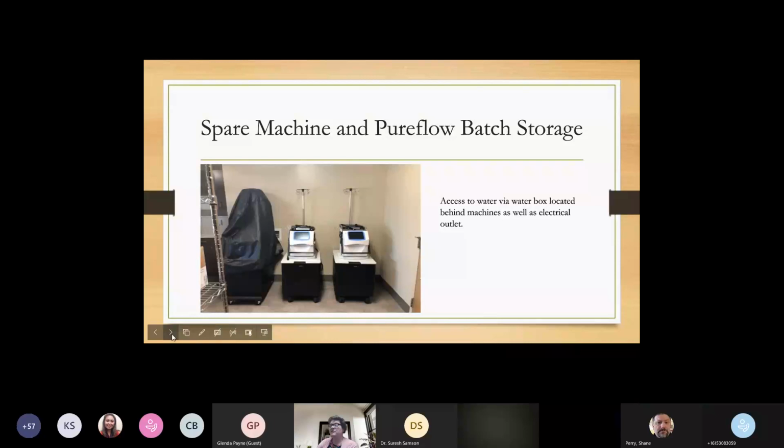So after we do a patient treatment, about every 2 to 3 days, we'll make a new batch of dialysate, and that allows us to create that in the supply storage room. And then when it's batch made, we can test it and take it to the treatment floor for the patient.